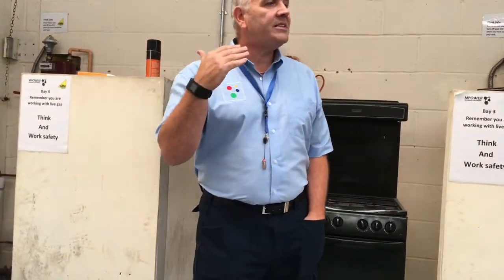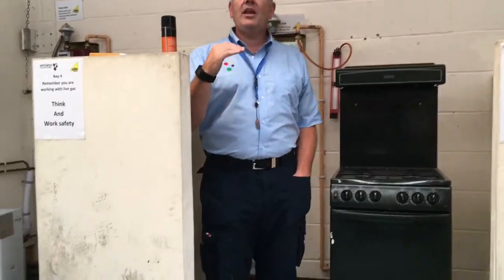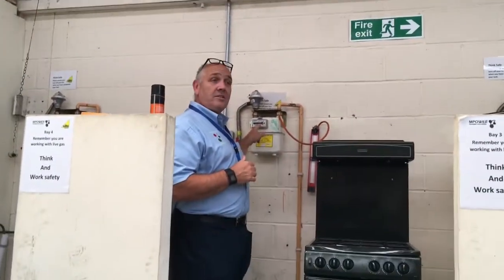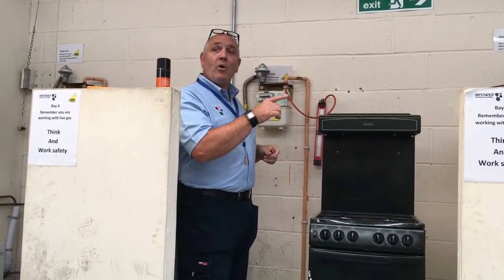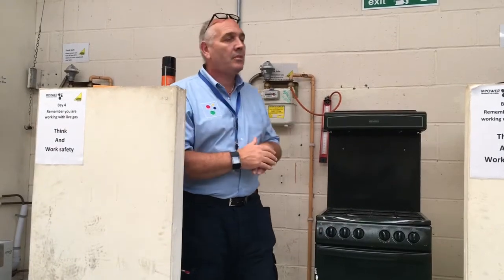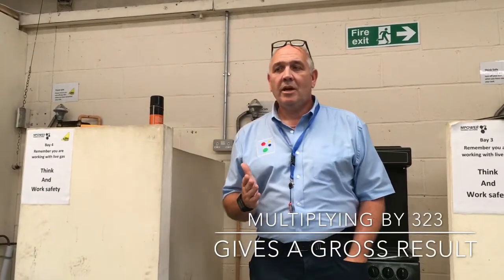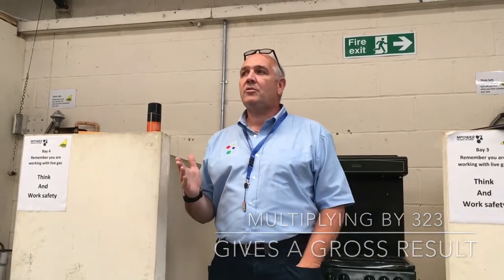Now you've got your figures on a metric meter. You subtract the first reading from the second reading, and that gives you a number. Remember that there is a decimal point on the meter, so it'll be 0.045 probably, or something like that. You subtract the first number from the second number. That leaves you with how much gas you've used. You multiply that number by 323.